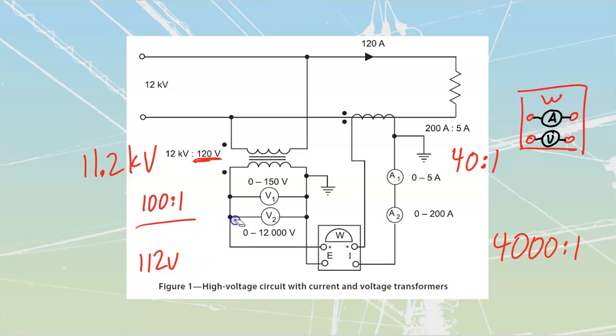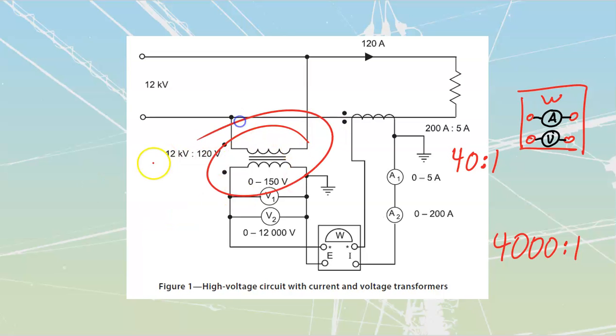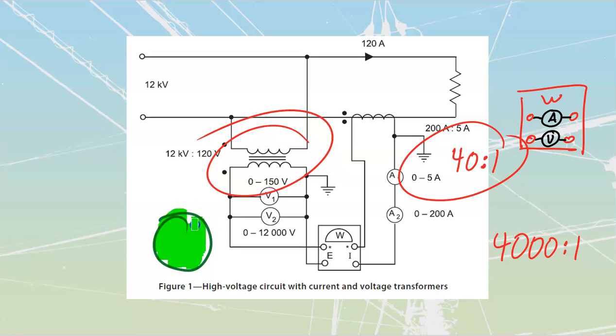Now, inside of an industrial application, what you will often see is that anytime there is going to be a place where there are PTs or CTs, hydro is going to take, and historically in the Fraser Valley, it's been green stickers. I don't know why. They've just had green stickers on there. You'll see this green sticker placed on the side of the meter, sometimes on the front of the meter, and maybe they've changed that now, but it used to be that, and it's just going to have an X80 or something like that written on it.